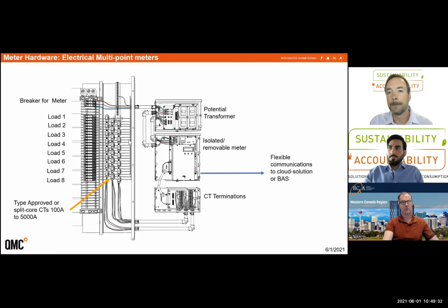plug loads. Another trick is you have multiple little circuits that are feeding a variety of loads, and you don't really care if you isolate each of those. You can run multiple circuits through the same CT. I mean, let's say you have 8 A-phase loads that are all going to small plug loads. You can run them all through the same CT, and it'll just totalize those for you. Again, saving on your hardware and installation costs in doing that. One thing I had to trim out of our presentation today, though, was doing the correct amount of metering.